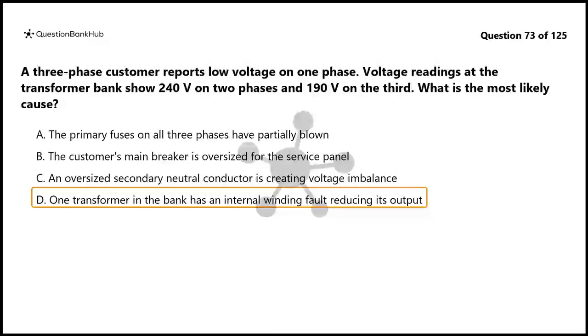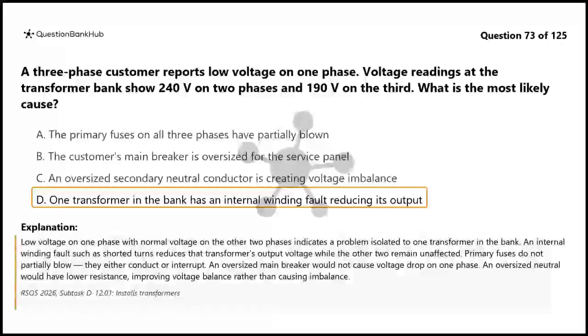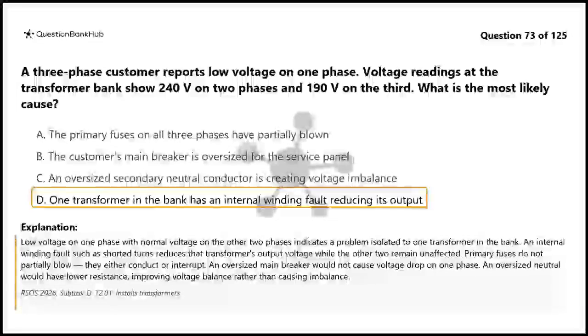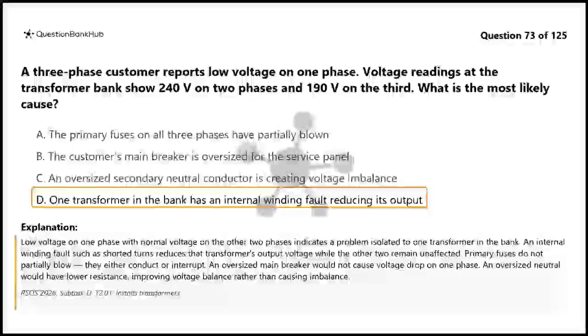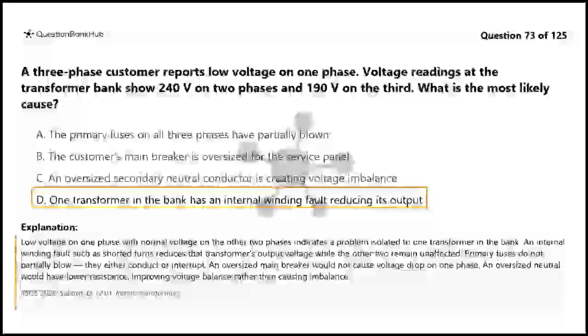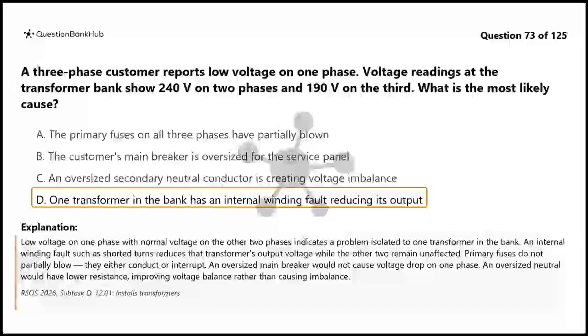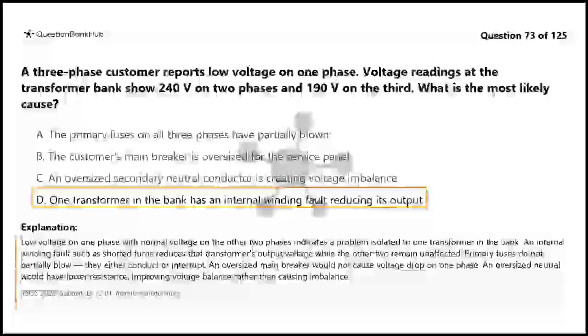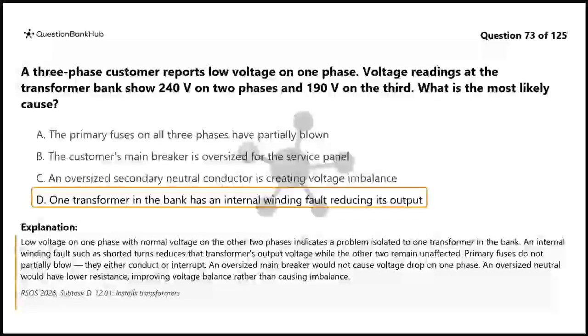The correct answer is D. Low voltage on one phase with normal voltage on the other two phases indicates a problem isolated to one transformer in the bank. An internal winding fault such as shorted turns reduces the transformer's output voltage while the other two remain unaffected. Primary fuses do not partially blow, they either conduct or interrupt. An oversized main breaker would not cause voltage drop on one phase. An oversized neutral would have lower resistance, improving voltage balance rather than causing imbalance.